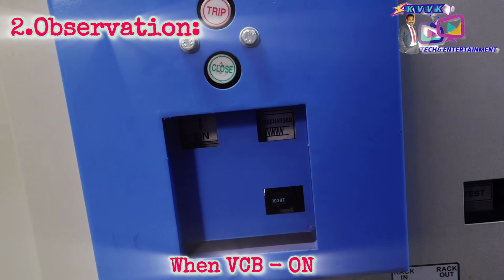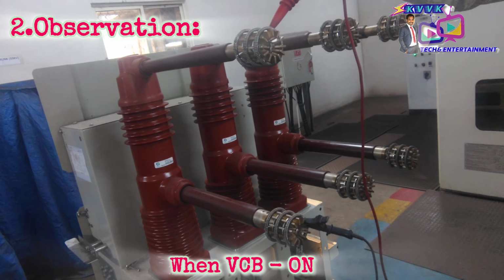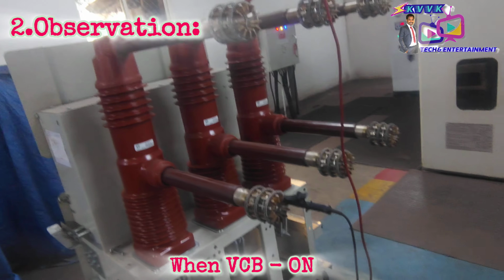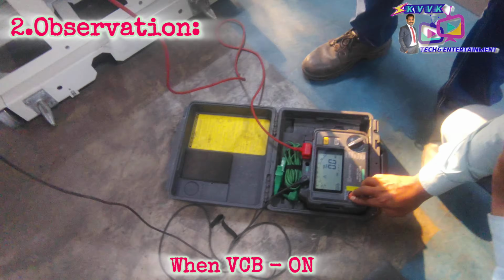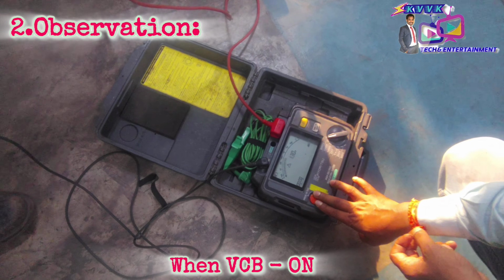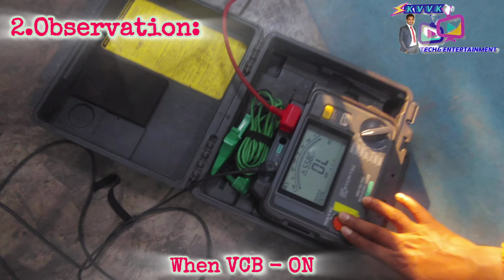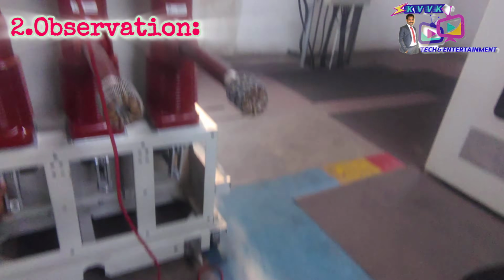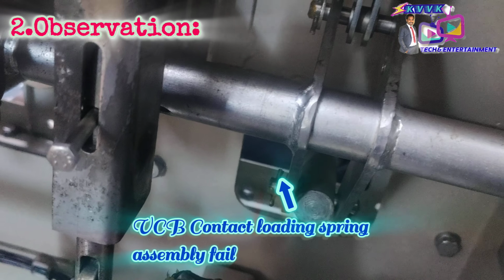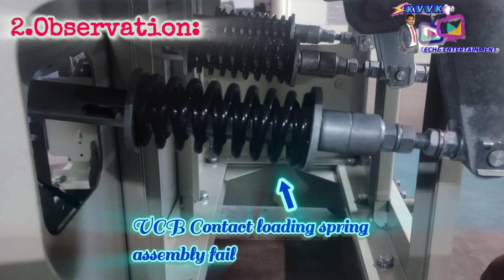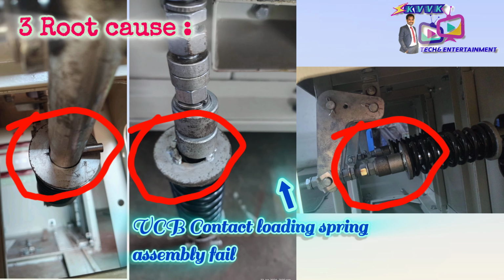For the observations, we followed visual and routine checks, or IR test and continuity with a Megger and multimeter, in closed and open condition. In closed condition, pole to pole B phase shows a high IR value instead of a short. So we checked the total VCB mechanism thoroughly related to B phase and found a broken contact loaded spring assembly for B phase due to a suspension lock welding crack.